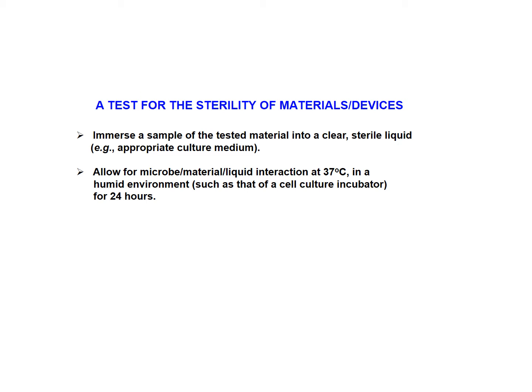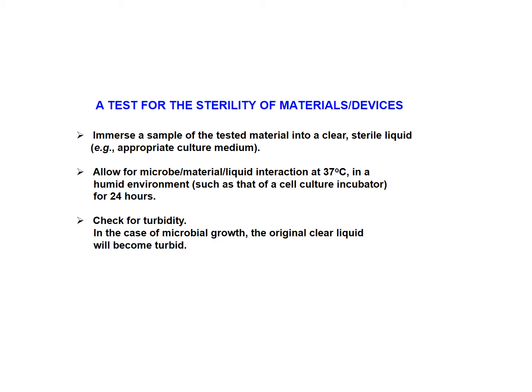Allow the containers in which the specimens are immersed to stay for a number of hours, let's say 24 hours, in an environment that simulates the body temperature, 37 degrees centigrade. At the end of that time, what one checks for is turbidity. If there is microbial growth, the original clear liquid will become turbid. And this is the evidence that the original specimen had been contaminated by microorganisms.